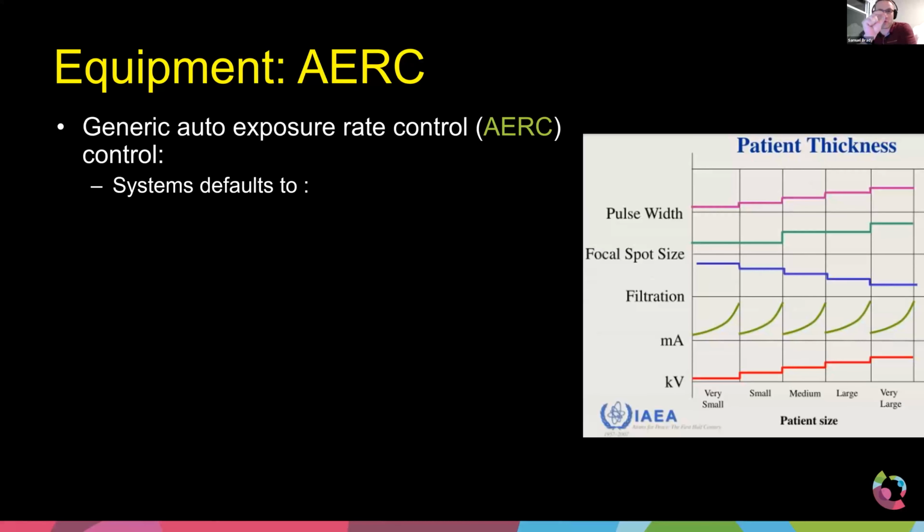And then, of course, there's the focal spot size. That's in the X-ray tube. The smaller the focal spot size, the better the spatial resolution. That was the same for CT as it is for fluoro. And then there's this thing unique to fluoroscopy, which is the pulse width. If we're going to send in one pulse after another, the idea is you want to keep them as short as possible. Up to this point, I've given you the example of 8 milliseconds. So we've condensed our 33 milliseconds down to 8. In reality, there are different types of pulse widths that we can control.